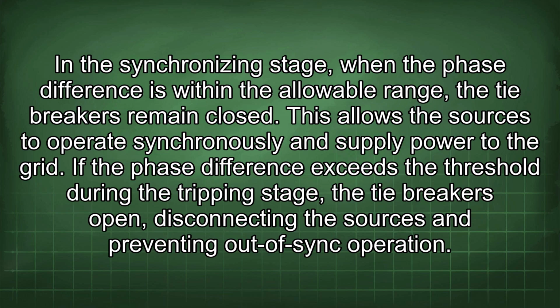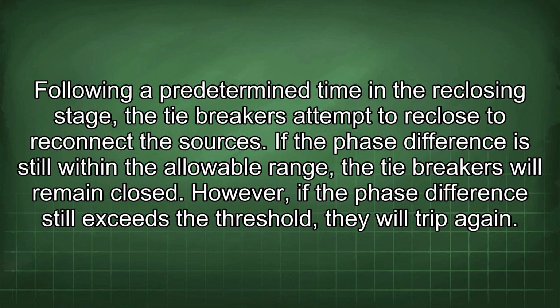If the phase difference exceeds the threshold during the tripping stage, the tiebreakers open, disconnecting the sources and preventing out-of-sync operation. Following a predetermined time in the reclosing stage, the tiebreakers attempt to reclose to reconnect the sources. If the phase difference is still within the allowable range, the tiebreakers will remain closed. However, if the phase difference still exceeds the threshold, they will trip again.